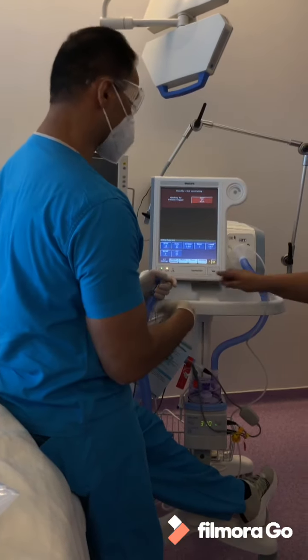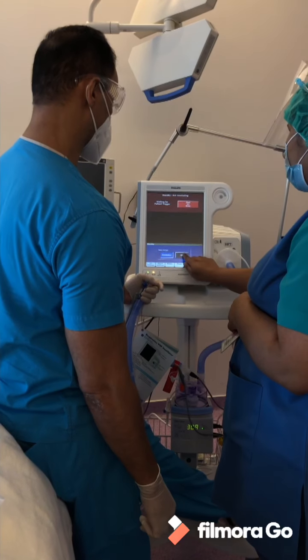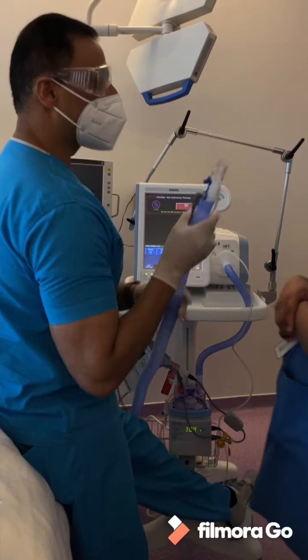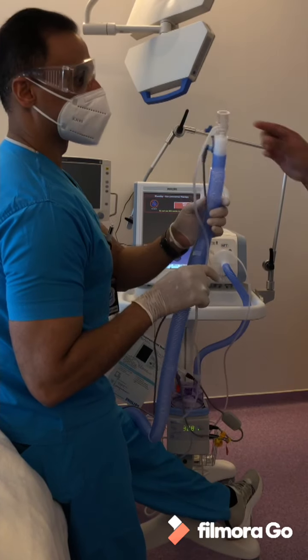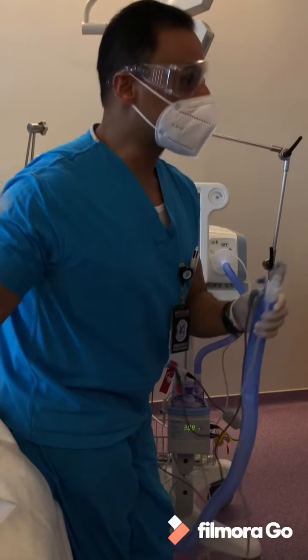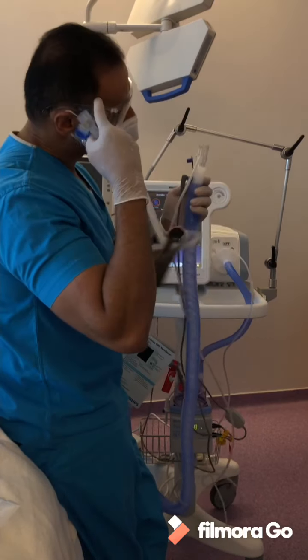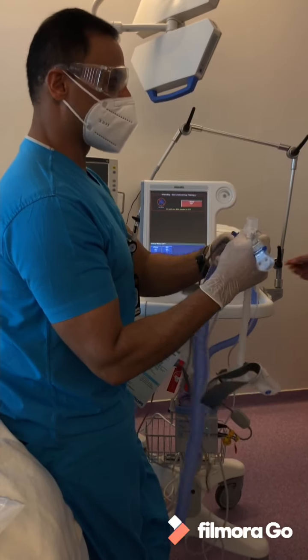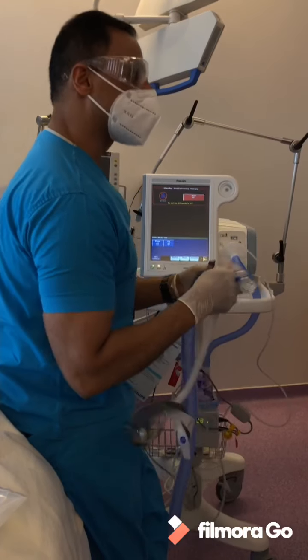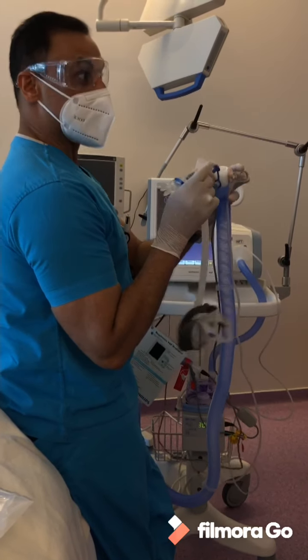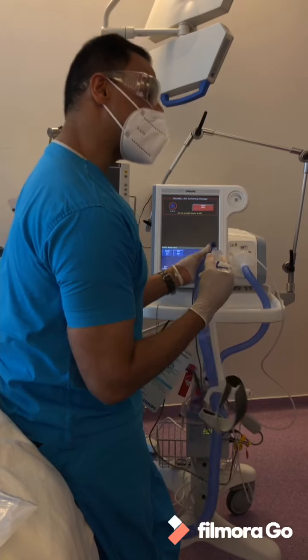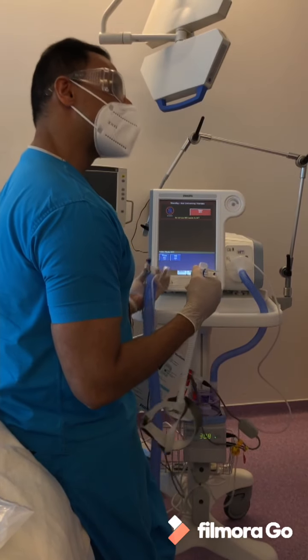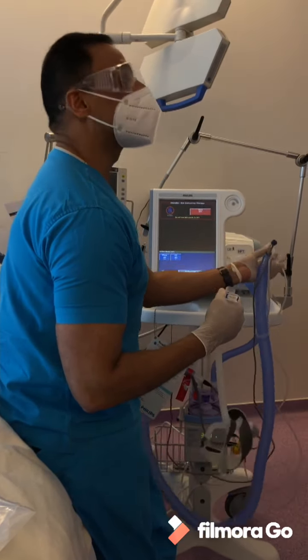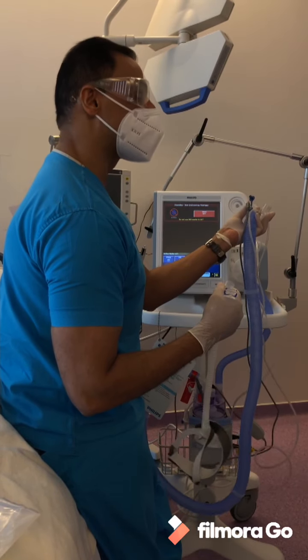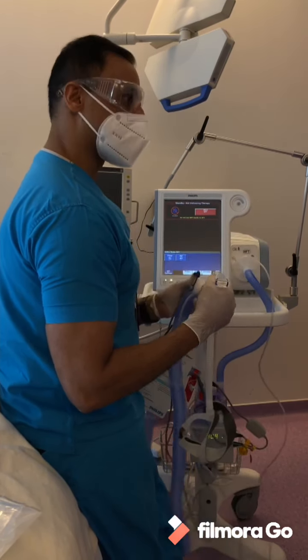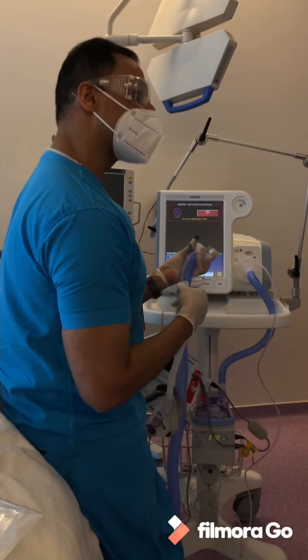One more, because I want to say something. Now, what to remove? Of course, if you try to connect, it will not connect. So, logically, you will remove this one. It's okay, you can keep it. It will not affect this. But it will matter if you want to change from high flow to BiPAP. From BiPAP to high flow, this will not change any parameters and will not give alarms. But when you change from high flow to BiPAP, it will give you an alarm.